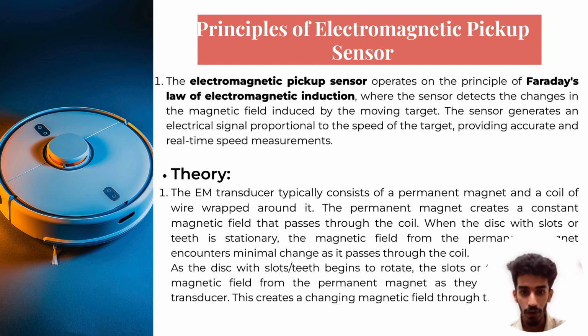Now talking about the theoretical aspects, the EM transducers typically consist of a permanent magnet and a coil of wire wrapped around it. The permanent magnet creates a constant magnetic field that passes through the coil when the disc with slots or teeth is stationary. The magnetic field from the permanent magnet encounters minimal change as it passes through the coil. As the disc with teeth begins to rotate, the slots or teeth disrupt the magnetic field from the permanent magnet as they come close to the transducer.